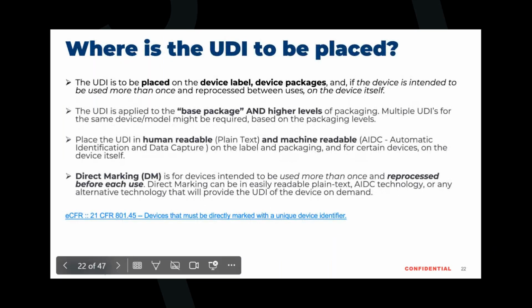Where is the UDI placed? The UDI is to be placed on the device label, device packages, and if the device is intended to be used more than once and reprocessed between uses, then it would require direct marking on the device itself. If it's being reprocessed and reused.